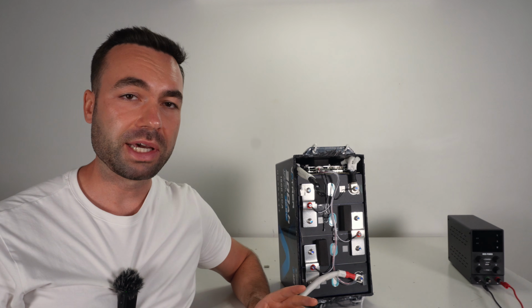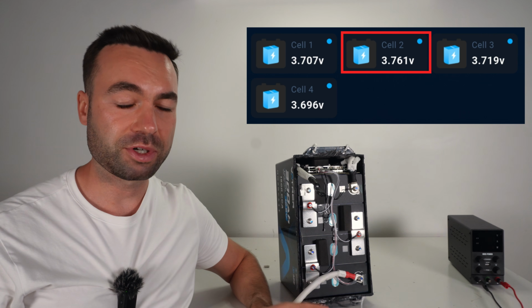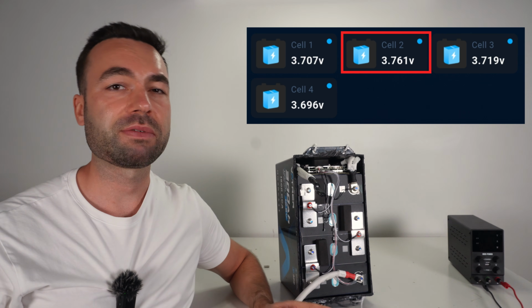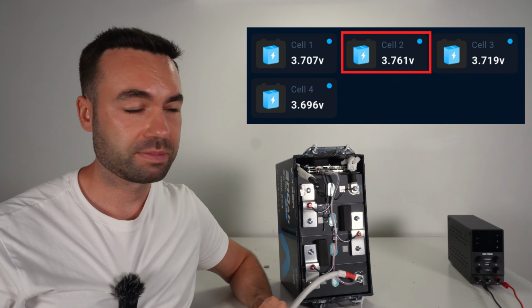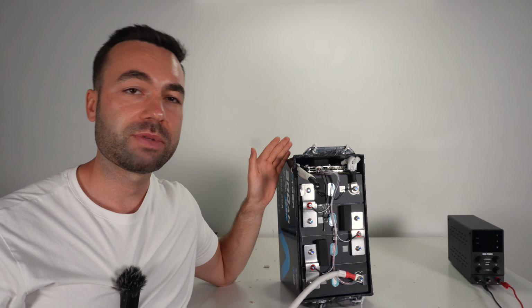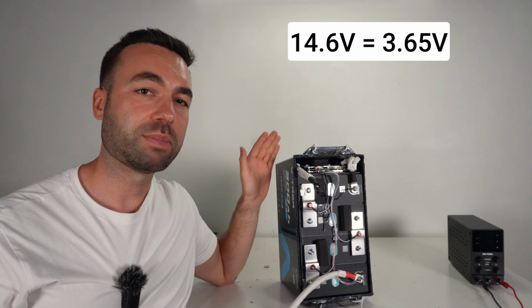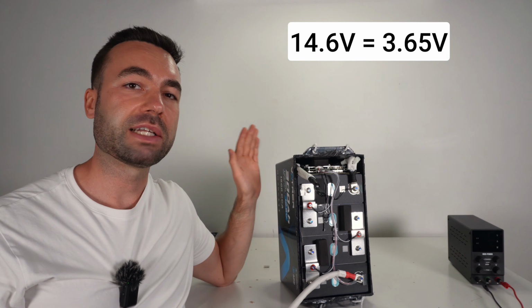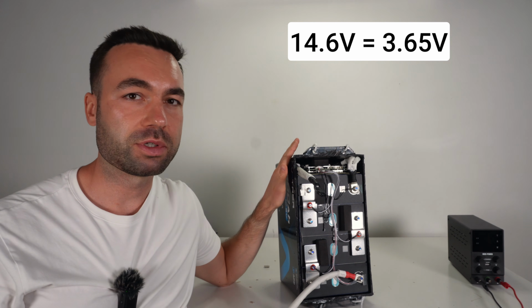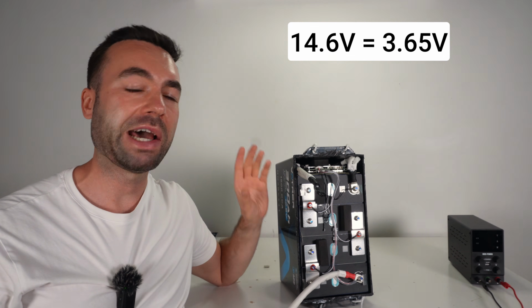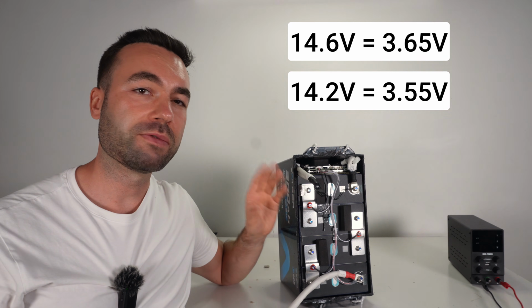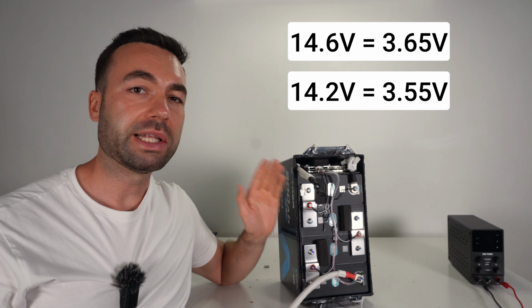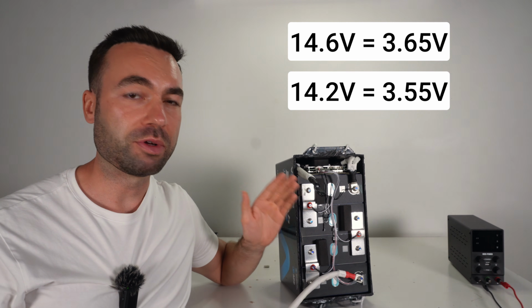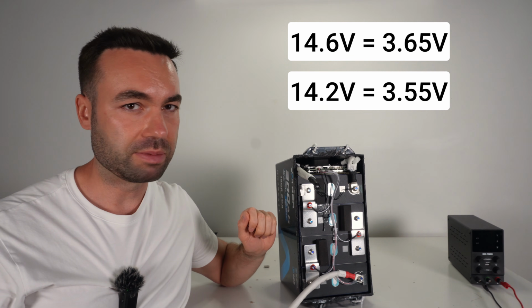Let's talk about the issue with the high voltage cutoff of 3.75 volts per cell. If you have a battery charger at 14.6 volts, that's 3.65 volts per cell. And if your MPPT is set to 14.2 volts, that's a maximum of 3.55 volts per cell.